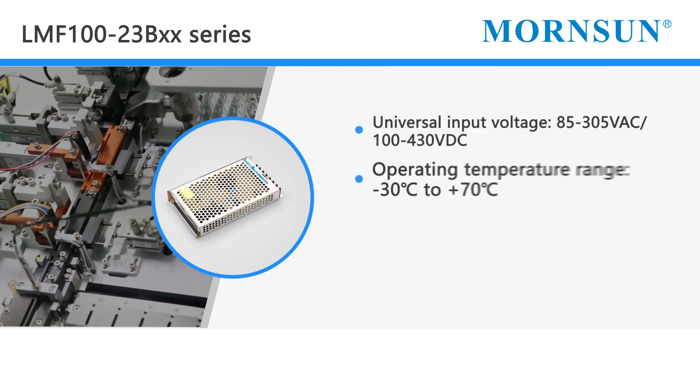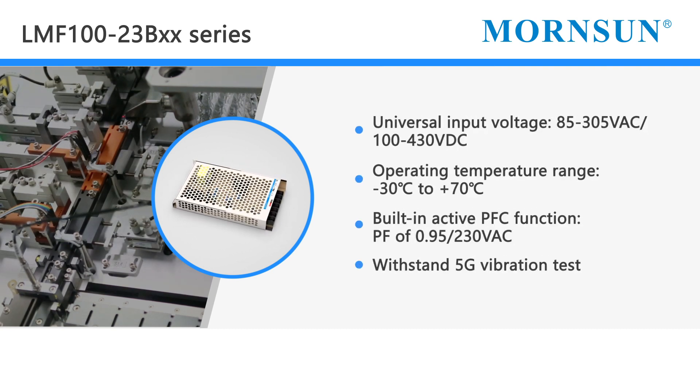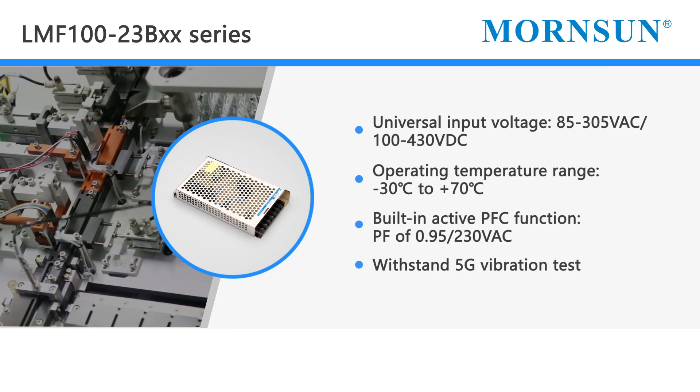Other features include a universal input voltage of 85 to 305 VAC, power range from 100 to 320 watts, operating temperature range from minus 30 to 70 degrees C, and the ability to withstand 5G of vibration.